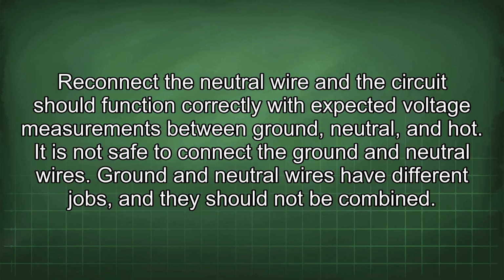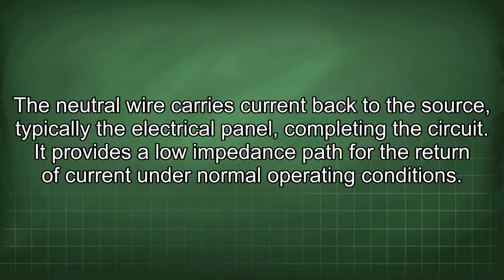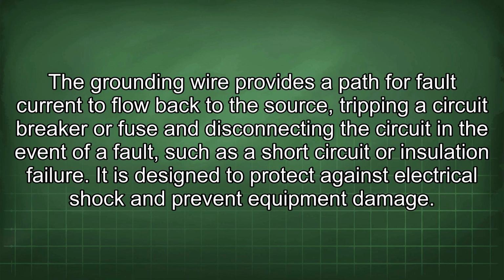It is not safe to connect the ground and neutral wires. Ground and neutral wires have different jobs, and they should not be combined. The neutral wire carries current back to the source, typically the electrical panel, completing the circuit. It provides a low impedance path for the return of current under normal operating conditions. The grounding wire provides a path for fault current to flow back to the source, tripping a circuit breaker or fuse and disconnecting the circuit in the event of a fault, such as a short circuit or insulation failure. It is designed to protect against electrical shock and prevent equipment damage.